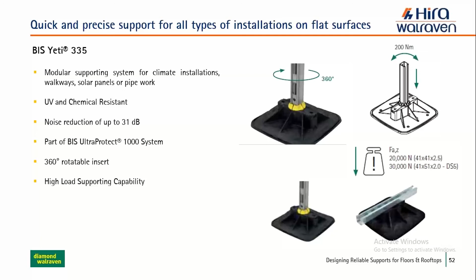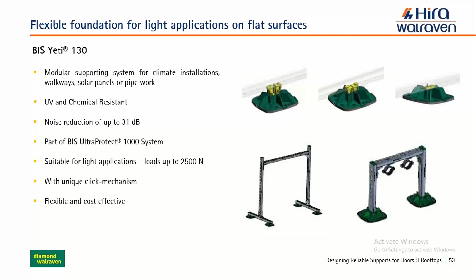The Yeti 130, as before, is also UV and chemical resistant, with noise reduction, and is a modular supporting system, but it is for lighter loads, so loads up to 2,500 Newton. This is where you use it. The difference between this and the other one is that it has a unique click mechanism. So you attach the channel with the holes, you connect them, and then you just click, and that's it. That's installed. So it's quicker in that way, although it's only for light loads.